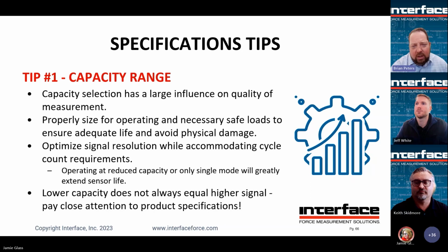Another thing to keep in mind too is what is fatigue rated. A lot of times, a couple 100,000s might be thought to be fatigue rated. In reality, no, that's fine. You can use a standard load cell. Or if you do have a fatigue test, where you are going to be doing millions of cycles, and the load cell isn't fatigue rated, you can often just go up in capacity, or at least choose the right capacity to where you're going to be operating in a realm where the sensor can easily tolerate the cycle count.